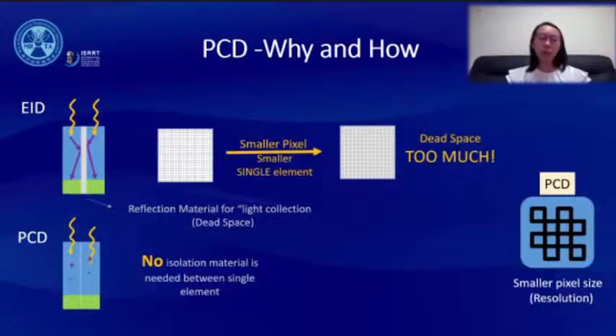Okay, the two-step conversion of EID requires reflecting material between every single element for controlling the visible light, and this layer is considered as a dead space for signal. We can make smaller pixels, that means smaller single elements, to improve the resolution in CT. But for the same FOV, increasing the number of elements causes too much dead space if we are using an EID detector. For PCD, with one-step direct conversion there is no need for isolation material between each element to control light. Ultra small elements are lined up one by one, stuck together without dead space, to perform ultra high resolution CT.